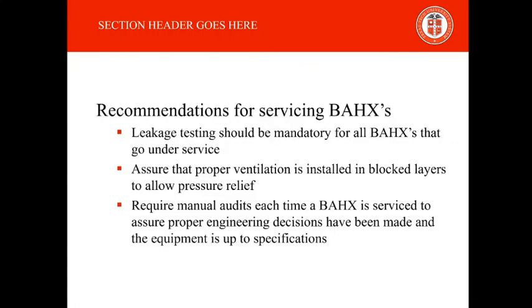First, I'll give my recommendations for servicing brazed aluminum heat exchangers. Recommendation number 1 is that leakage testing should be mandatory for all brazed aluminum heat exchangers that go under service. Recommendation number 2 is to assure that proper ventilation is installed in the blocked layers to allow pressure relief. Recommendation number 3 is to require manual audits each time a brazed aluminum heat exchanger is serviced to assure proper engineering decisions have been made and the equipment is up to spec.